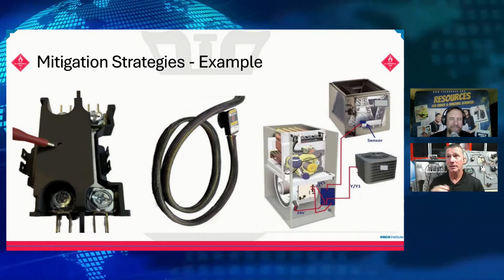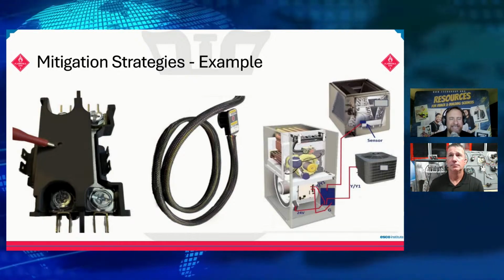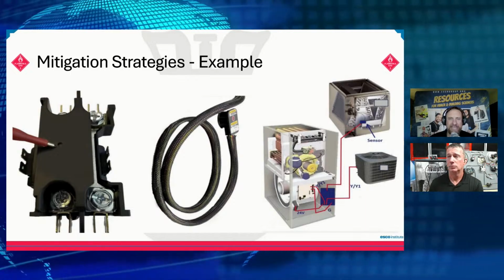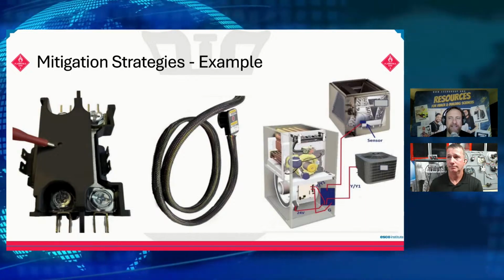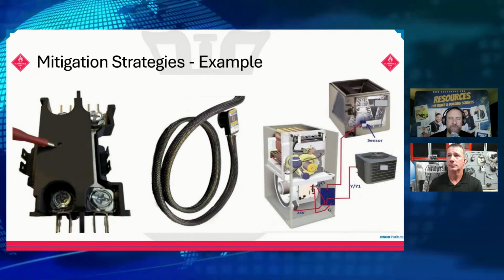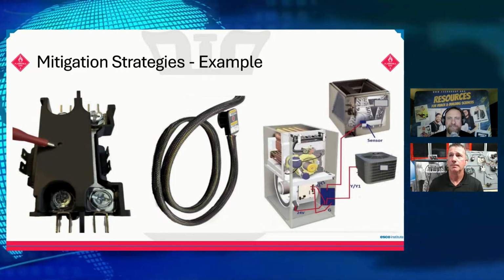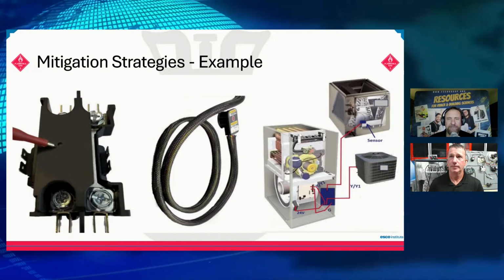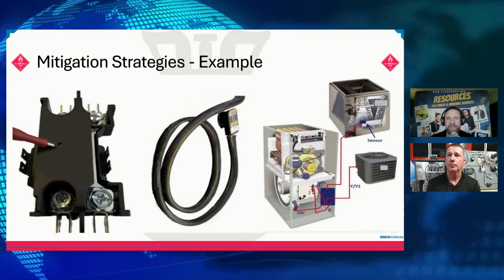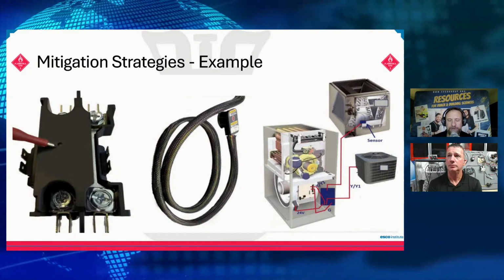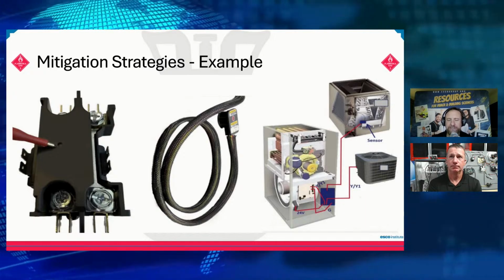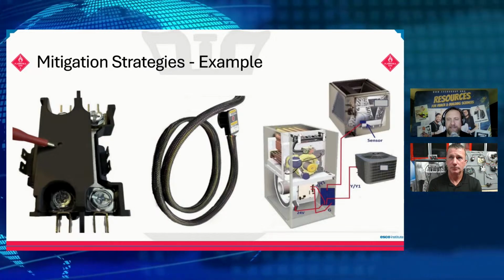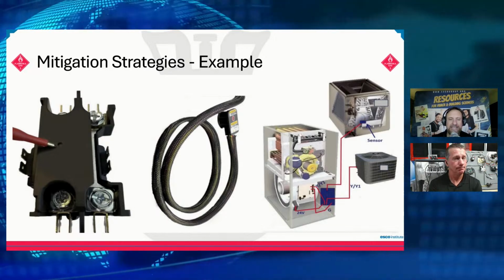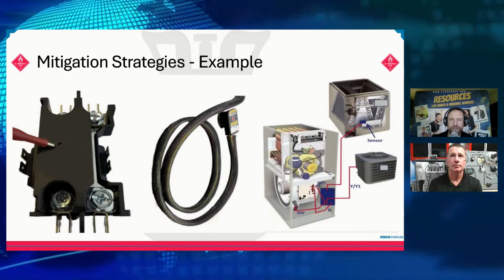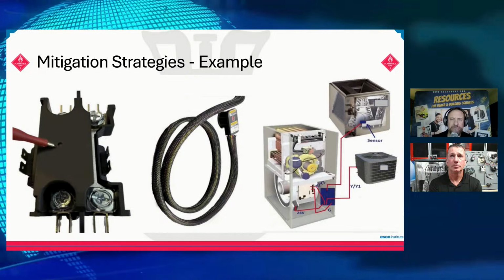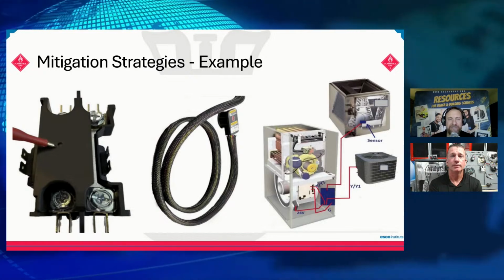If we think about it, whether it's a gas furnace or an oil furnace, when we end that W call, if it's a gas furnace we immediately lose our gas valve, losing our fuel for combustion. If it's an oil furnace, same thing — we immediately shut off the fuel, but we still run the fan. So the mitigation for the oil furnace is still in play, just like a gas furnace. We end that W call and let the furnace take care of itself. Even if we don't have an oil furnace with the controls built in, adding that mitigation board gives us the same solution.